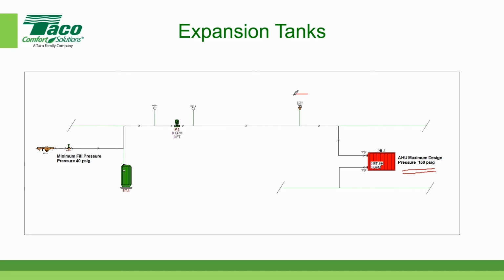And we have a pressure relief valve or safety relief valve. We want to make sure that the pressure does not reach the maximum design pressure. So we're going to set the relief valve at minus 10% of the equipment rating. So the equipment is 150 minus 10% or minus 15. So the pressure that we're going to set our safety relief valve is 135.